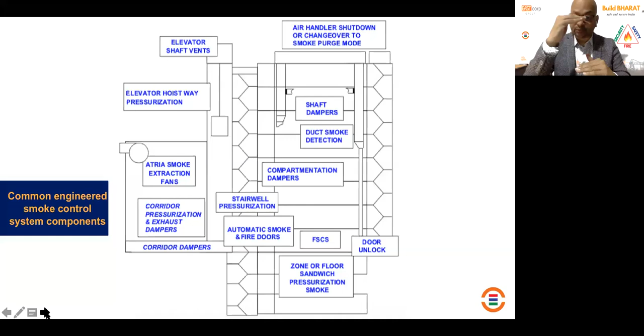So fire door management is also part of your smoke management. It has to be taken into consideration. If you don't take that into consideration, then your pressurization calculation will also fail. Then your dampers: how are we allowing these systems to ventilate between the floors? How are we going to manage? By using the dampers. The damper is the one that you are going to operate automatically, taking the input from the fire alarm system, which will open and close so that it creates that pressure and doesn't allow the smoke to pass through from one area to the other area.